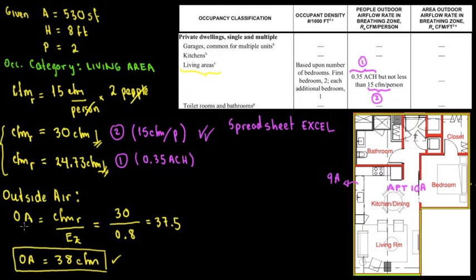And also this outside air, what you see here, outside air, you have CFM required. They have different notations in ASHRAE, like Voz. It's totally different. For example, you're going to have for ASHRAE Voz or something like that. But I don't want to confuse you, so that's why I'm making it easier: CFM required and outside air. Now I'm going to make another example very quick so you can see what the difference is.